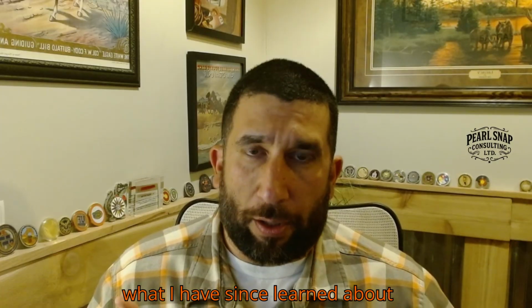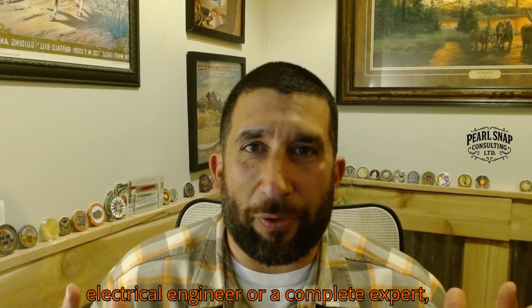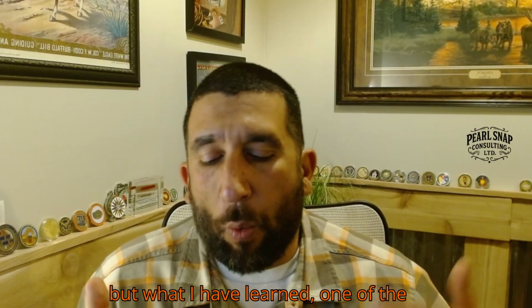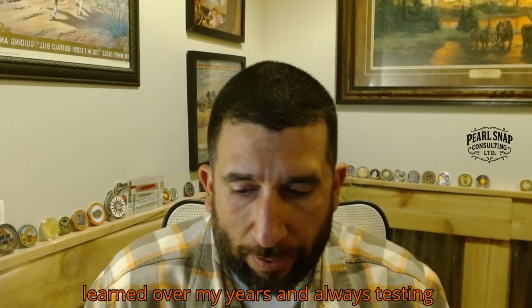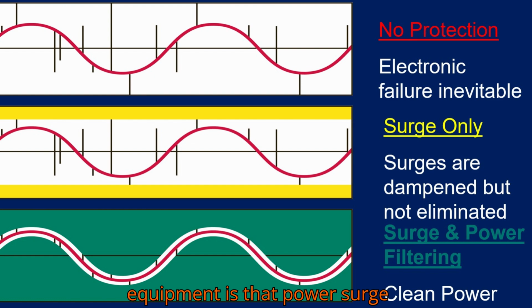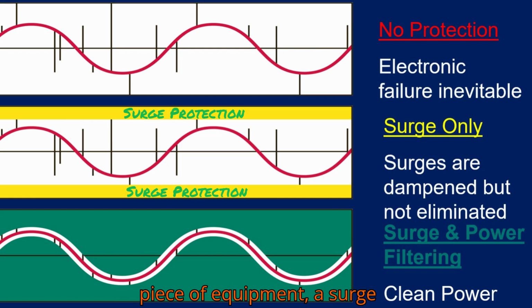What I've since learned about electricity, I'm not an electrical engineer, but from testing EOC emergency power systems and equipment, one reason that system failed is that power surge protection only activates within a limit. When a surge hits a facility or piece of equipment, the surge protection turns on once it hits a certain threshold of electrical surge, protecting the equipment at that high level, hence the term surge protection.